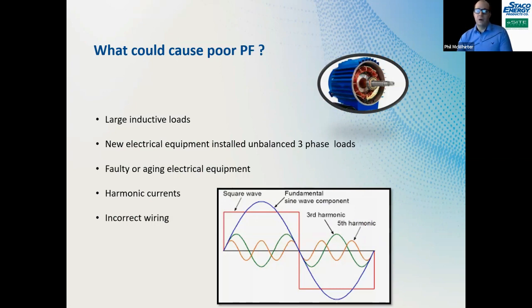Say you install a new piece of electrical equipment on your A phase, and you keep installing new equipment on your A phase. You're going to get an unbalanced phase. That's going to cause poor power factor. Maybe you have some aging electrical equipment that's causing issues, which could cause poor power factor as well. That could also introduce harmonic currents, which could affect your imbalance and cause more apparent power to be needed to drive your equipment. Incorrect wiring is also really big.